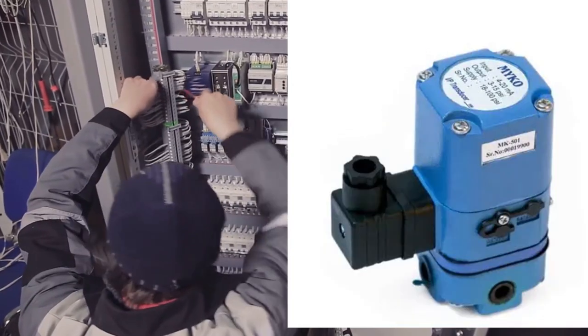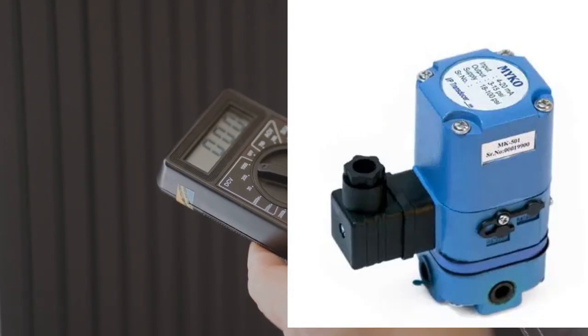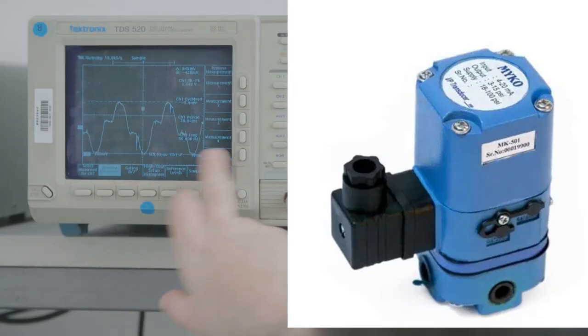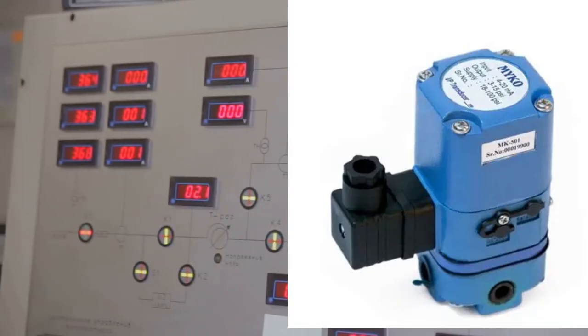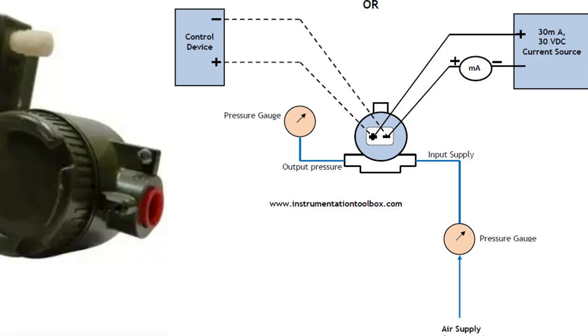Electrical issues are another classic. If your input current isn't right, say it's not landing in that sweet 4-20 milliamp range, you can't expect good output. Wiring faults, loose connections, or even ground loops can drive you nuts with sporadic or incorrect operation. I've lost count of how many times a simple wiring check would have saved hours of troubleshooting.